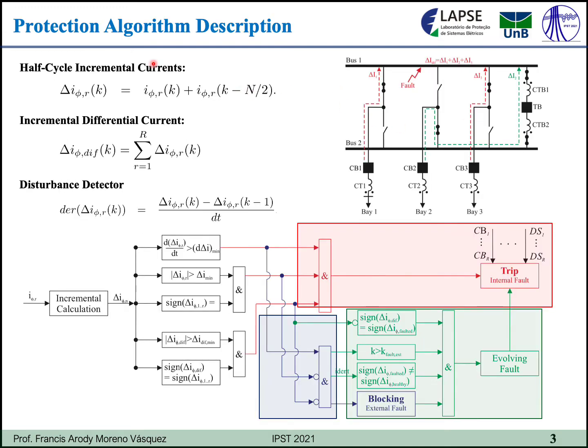So, in order to explain the proposed protection algorithm, I will use this simple power system where I have a bus 1, bus 2, and bay 1 and bay 3 are connected to bus 1, and bay 2 is connected to bus 2. These buses are interconnected through a tiebreaker, and when a fault occurs in bus 1, for example, the currents are calculated. The differential current is calculated as a sum of the contributions, and also when a fault occurs in bus 1, all the contributions have the same polarity. All of them flow into bus 1.